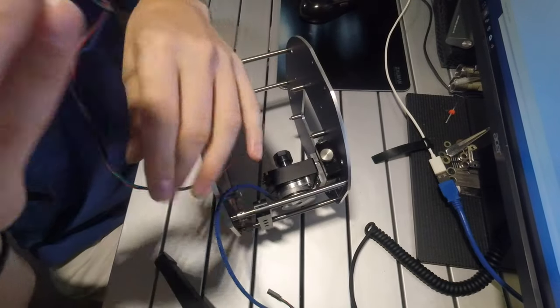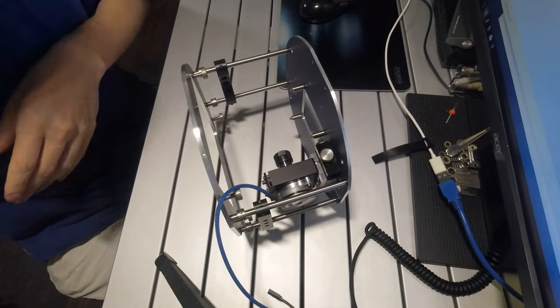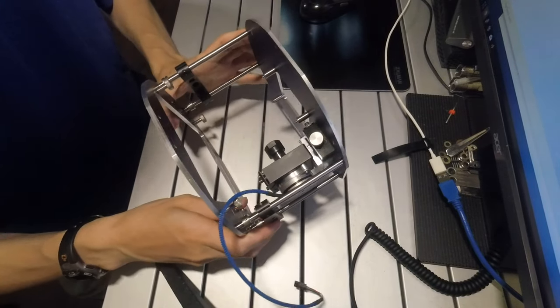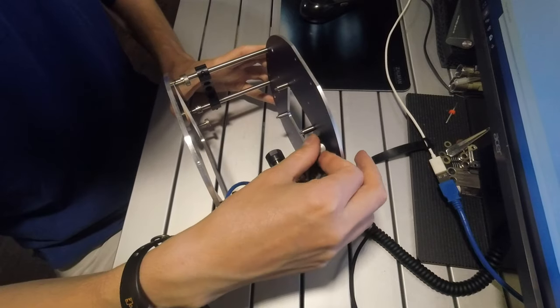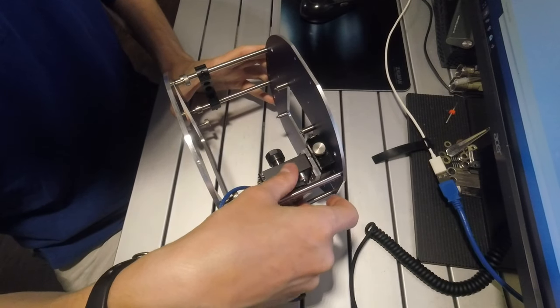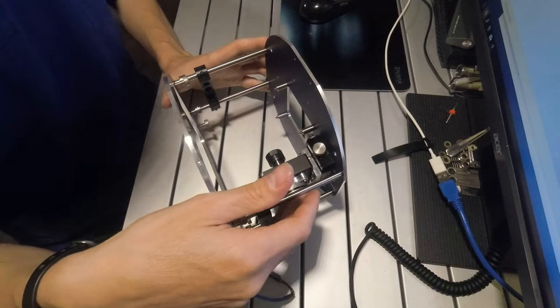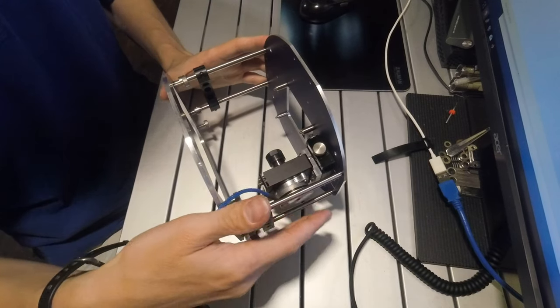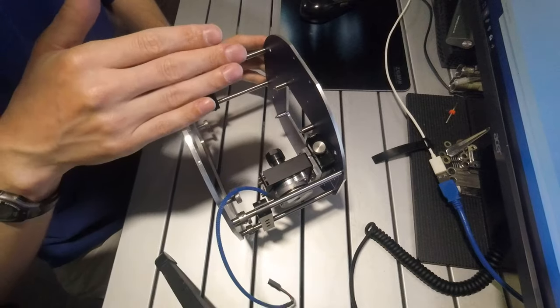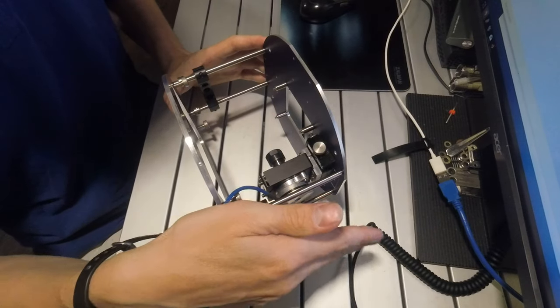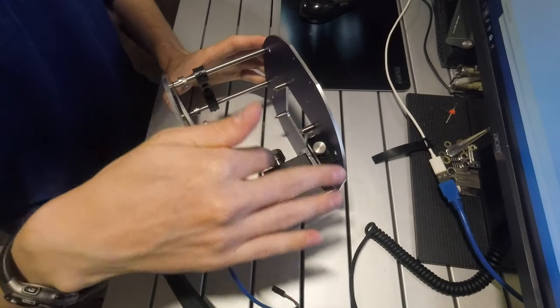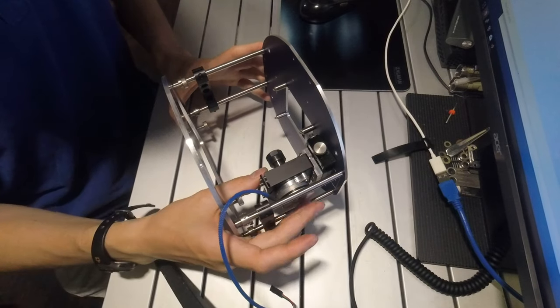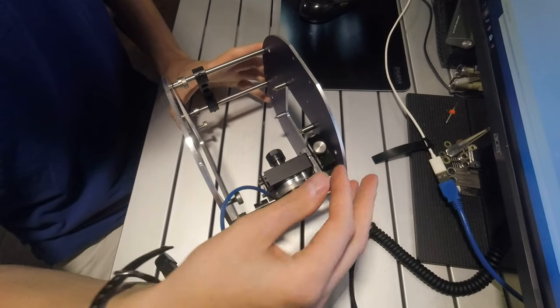So to fix that alignment issue I've designed an insertable stage which uses translation stages and a kinematic optics mount to assist in the precision adjustment of the rotation axis of the stepper motor in order to make it perfectly perpendicular to the axis of the imaging sensor and perfectly centered.